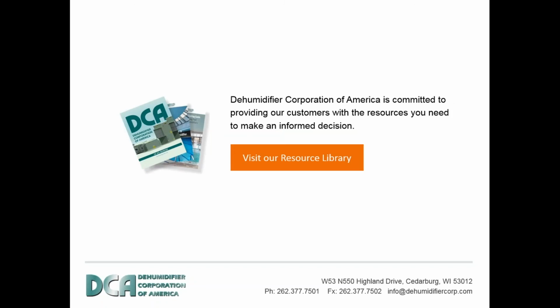Obviously, the pool dehumidifier is probably the key component of all HVAC in any pool room. And certainly the amount of moisture that evaporates into the space has got to be taken very seriously, because you will cause mold and mildew problems quickly, and you will then repair that. Many times it's a tear down, and then you'll add a dehumidification system after that. So let's do it right the first time. If there's a problem, if there's any suspect that the unit's too small or too big, let us run the loads to make sure that the new system is going to be exactly what you need to take care of the problems.